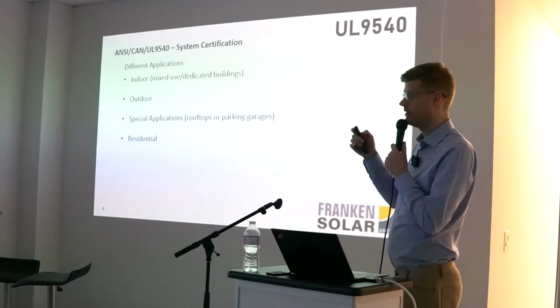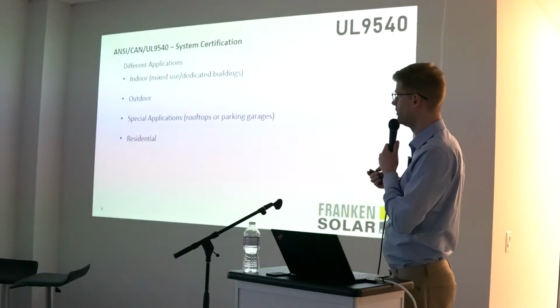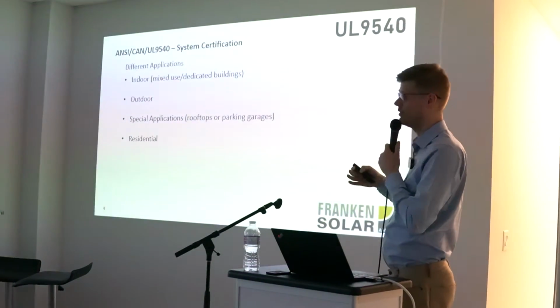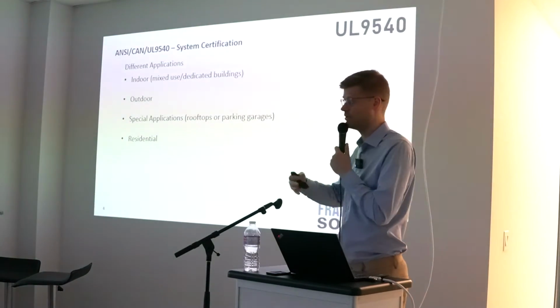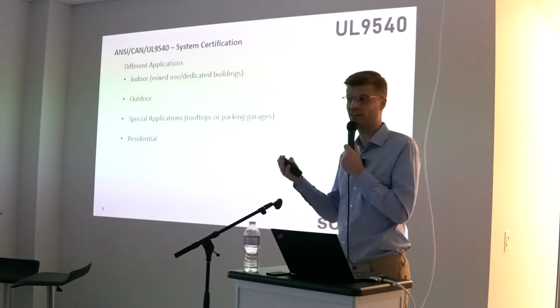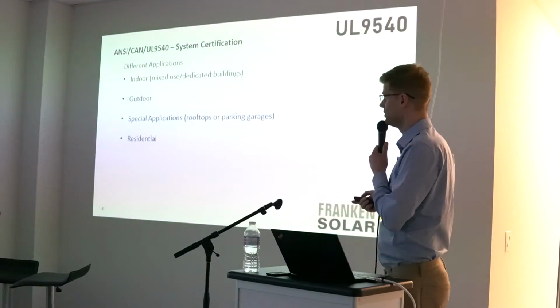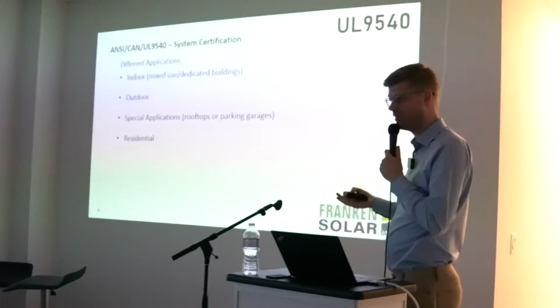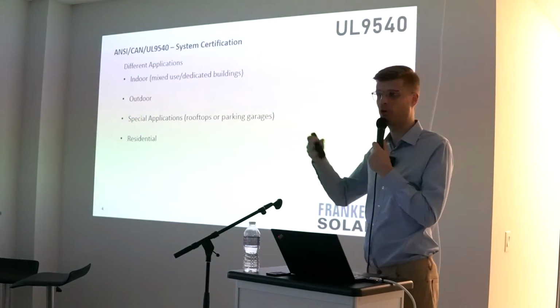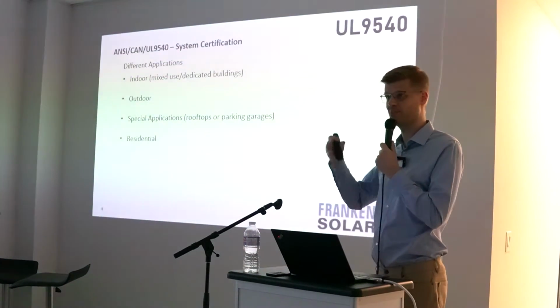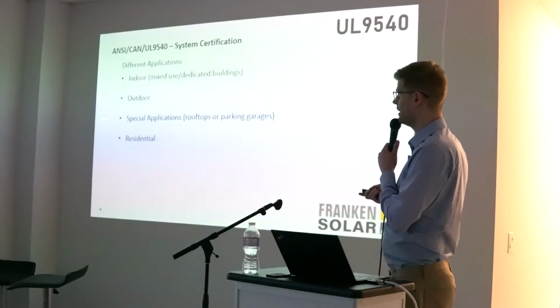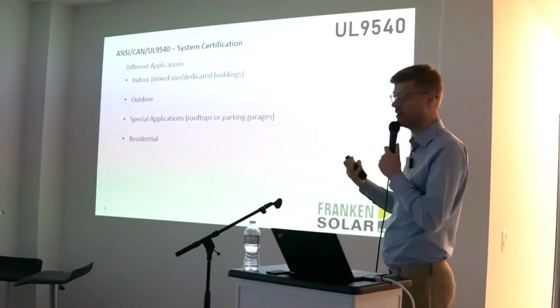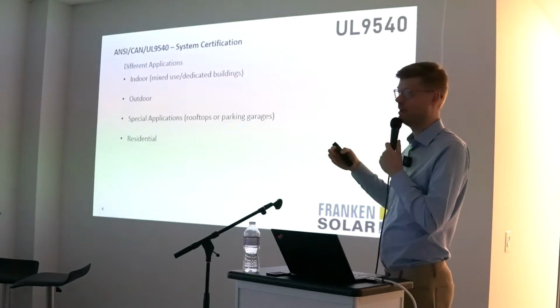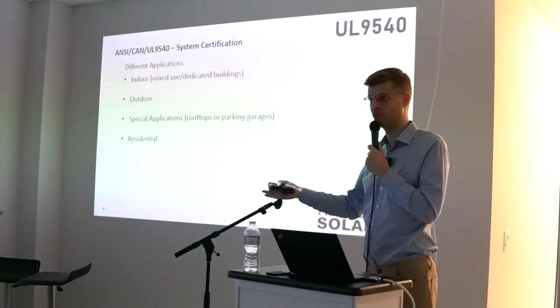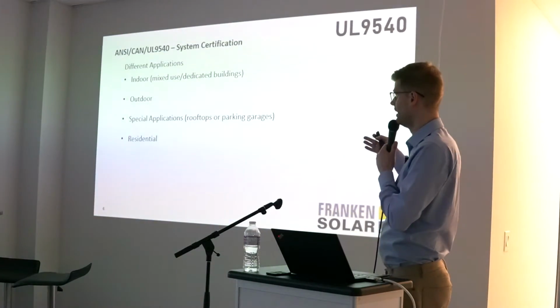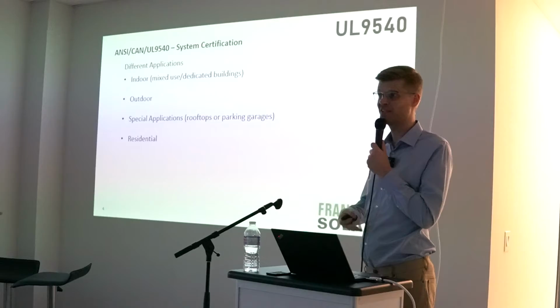The code categorizes in four main categories. One main category is indoor systems, when you have, let's say, a mixed-use building, like a storage facility, or a dedicated building, or even a dedicated room, like a container, where you put your system in. We have outdoor systems, not very common for residential, but these are standalone on a concrete pad, where they have their own HVAC systems and heating systems, fully weatherized. Then we have special applications that don't really apply to what we are doing and probably what you're doing. These are systems that can be co-located besides HVAC systems on commercial rooftops, not very common here again, or they can be placed in parking garages to assist EV charging.